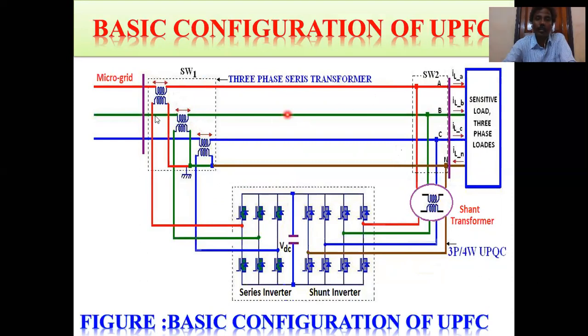So this is the microgrid, smart grid or transmission section, and this is the transformer section and series inverter, which injects the voltage, and this is the shunt inverter connected through a DC battery or capacitor. This is the shunt transformer. This is a sensitive load. If this is absent, then it is a three-phase four-wire UPQC, Unified Power Quality Controller.